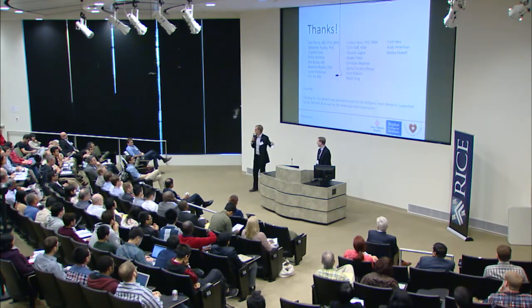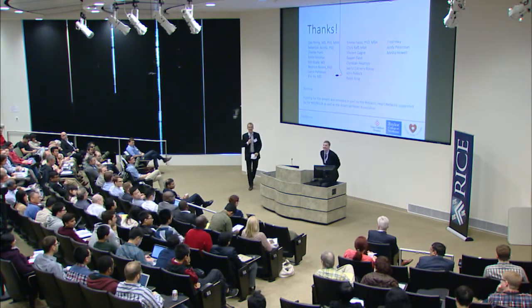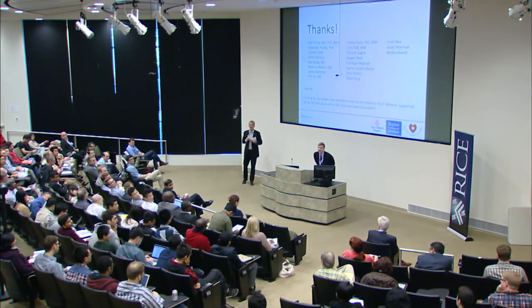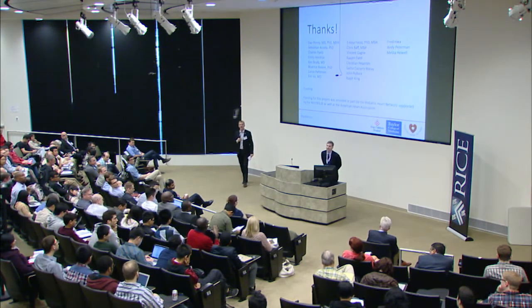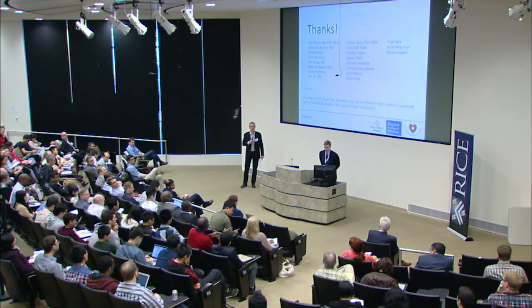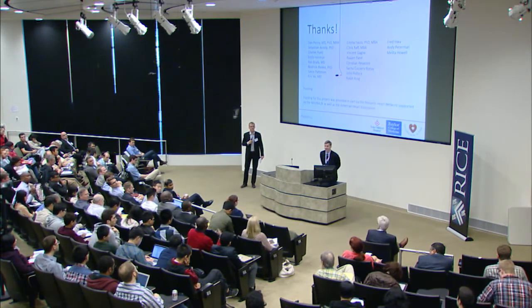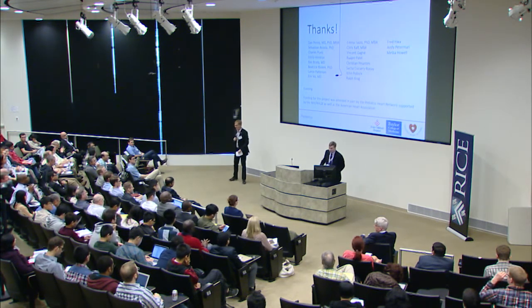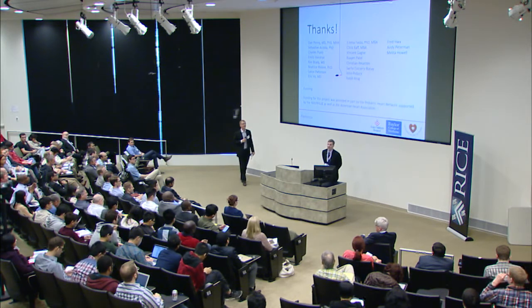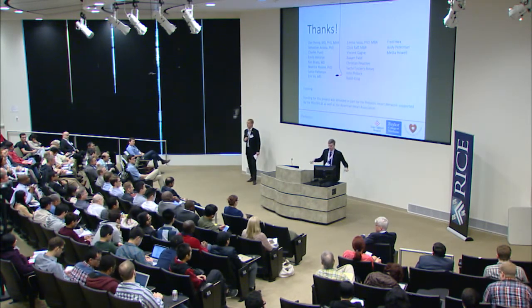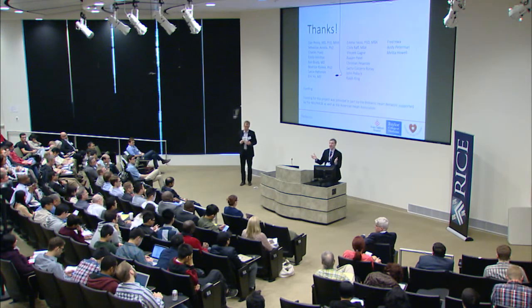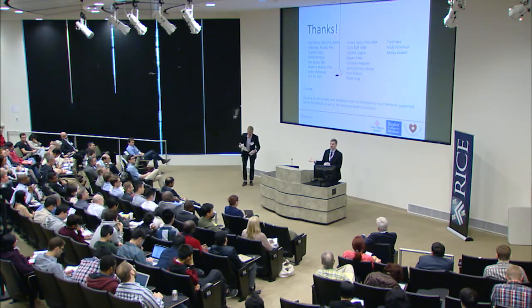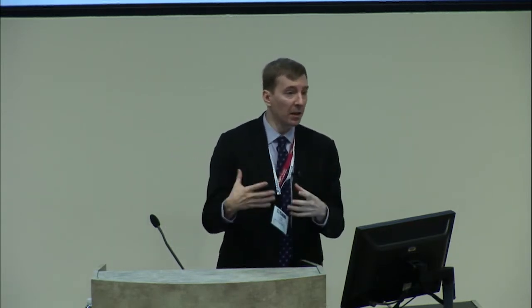How customizable is Sickbay to avoid false alarms? Physiological data is different from patient to patient and from patient population to patient population — is it highly customizable? There are kind of two answers to that. The platform itself is simply designed to provide the algorithm with all the data available, because what's noise to one algorithm may actually be signal to another. Having the platform make that decision is not really correct.